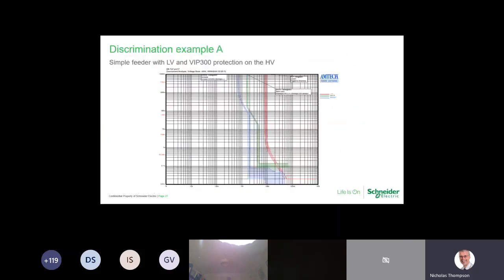Now, when you get a decision to make, this is an example where you've got a time limit fuse and a VIP. This first picture is again from Amtech, which is one of the proprietary software packages used for protection studies for both HV and LV. We've got red for the time limit fuse, green for your first LV, and blue for your second LV. You can see the green is crossing over into the red, and the blue is also crossing over into the red as well. So we've got a potential problem there.